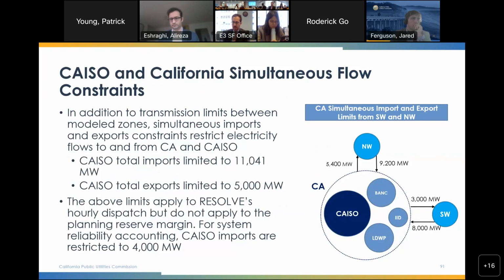In addition to the interzonal flow limits, we also model CAISO and California-wide simultaneous flow constraints. The CAISO total imports are limited to 11,041 megawatts, and CAISO total exports are limited to 5,000 megawatts. These limits apply to Resolve's hourly dispatch, but do not apply to the planning reserve margin. For system reliability accounting, CAISO imports are restricted to 4,000 megawatts.